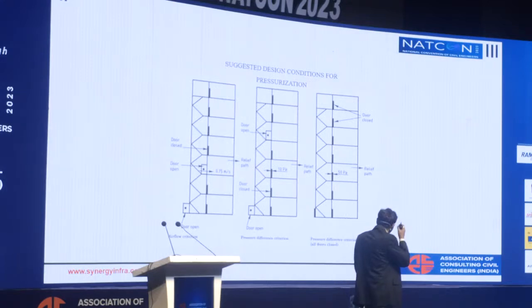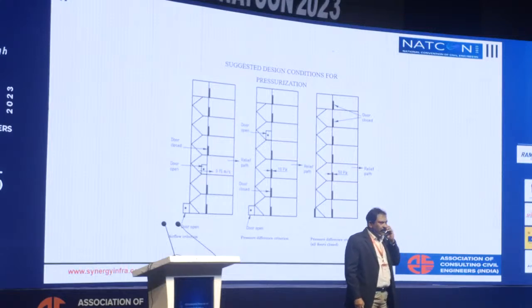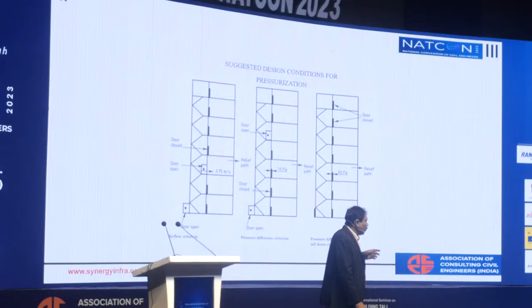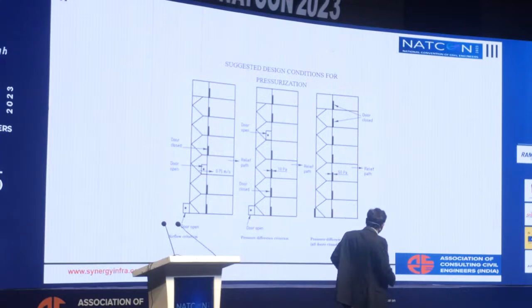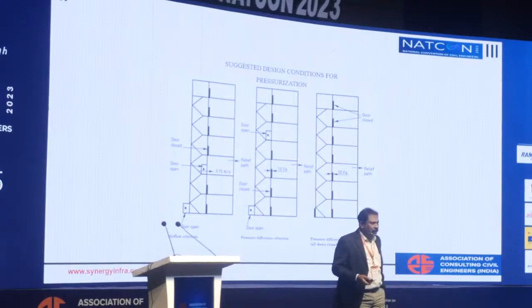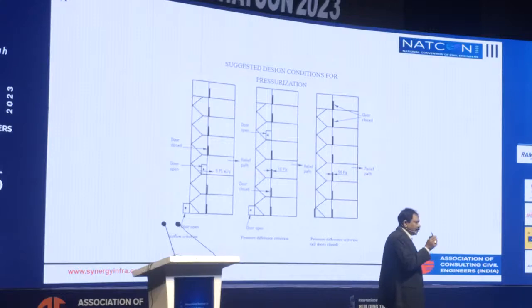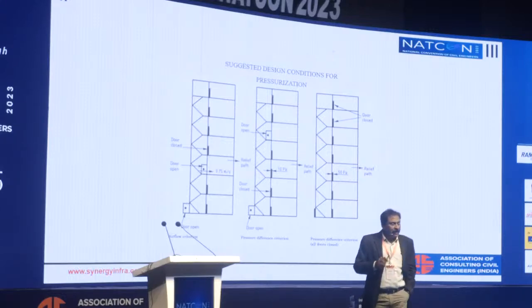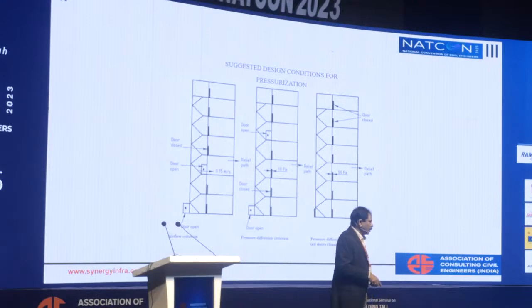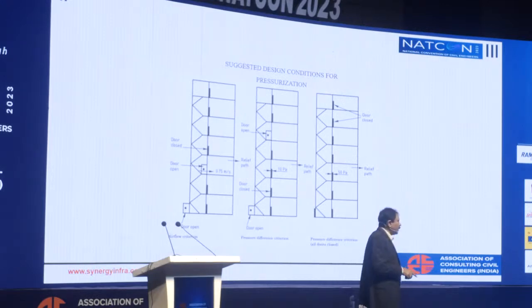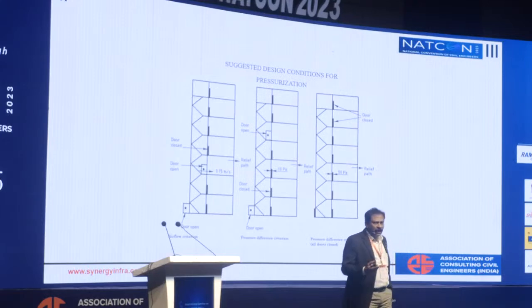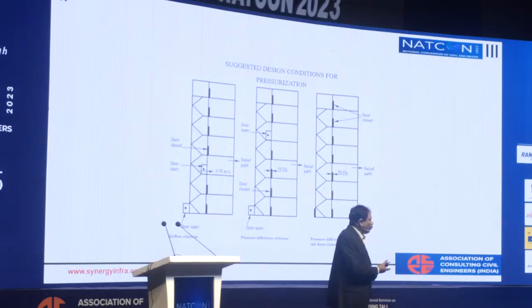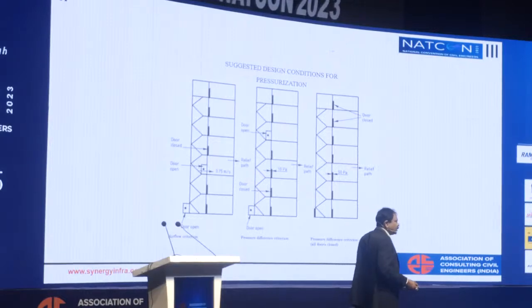Unfortunately, we don't have any code with respect to pressurization in India, so we have to follow some of the international codes. This is from the British code, and how many doors are to be opened in case of an eventuality is also not specified anywhere. Our code says only 50 pascals in the fire staircase and 25 to 30 pascals in the fire lift lobby or fire shaft. The problem is this applies only when all the doors are closed. But in case of any fire, usually the door where the event happened, as well as the ground level exit, and maybe 1 or 2 other doors also have to be considered as open. Once you open the doors, this pressurization level will go down.